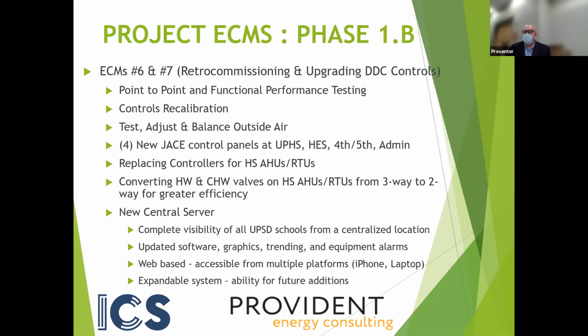There's quite a bit of HVAC equipment that has been deemed in good shape and able to remain in place. As a result, we're going to be doing things like point-to-point checks, functional performance testing, recalibrating controls on that equipment. It's a very detailed and thorough process that will give us a list of things we need to either repair, calibrate, or fix. But at the end of the day, we're going to get these pieces of equipment back up and running as they were designed, and also to meet existing code.